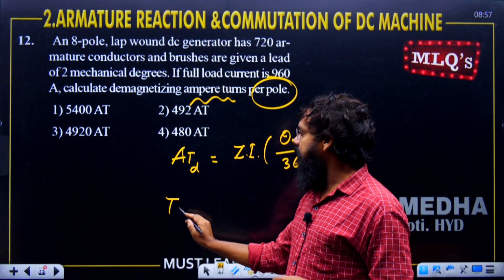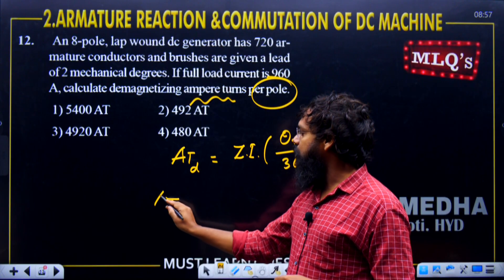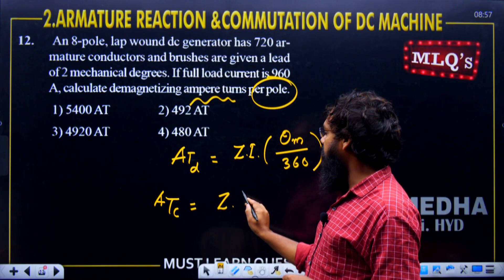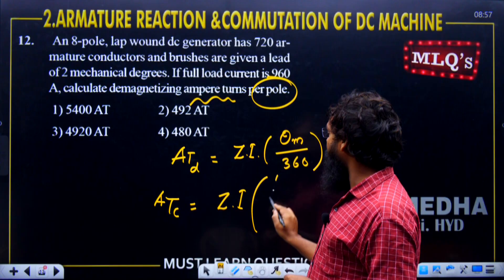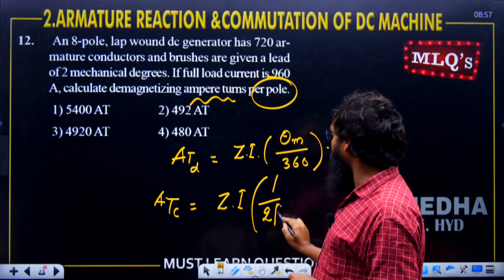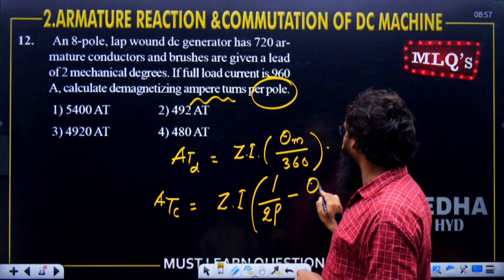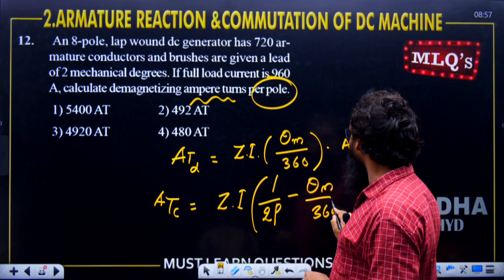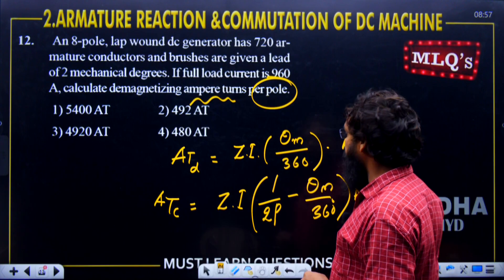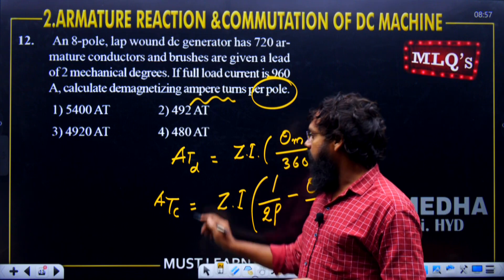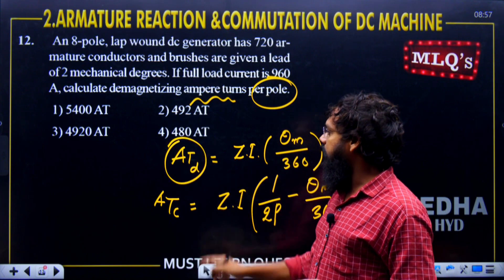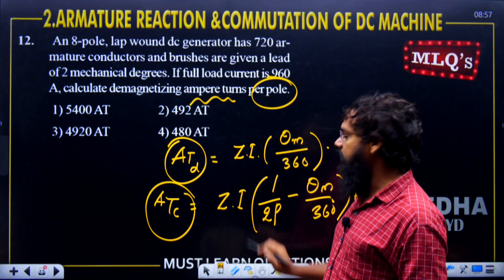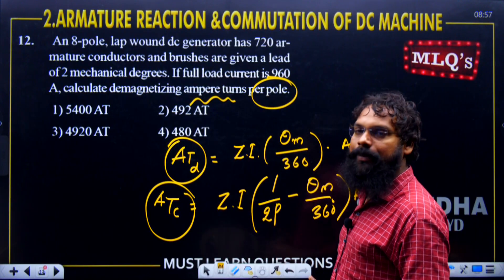If you get a question about cross-magnetizing ampere-turns, the formula is: AT = Z × I × (1/(2P) − θ_m/360). These are the direct formulas for the demagnetizing component current and the cross-magnetization component.